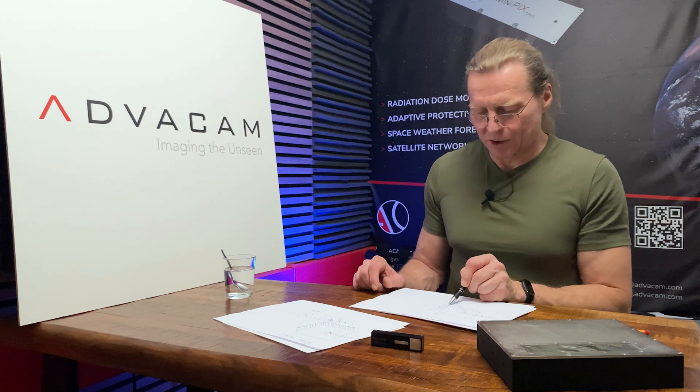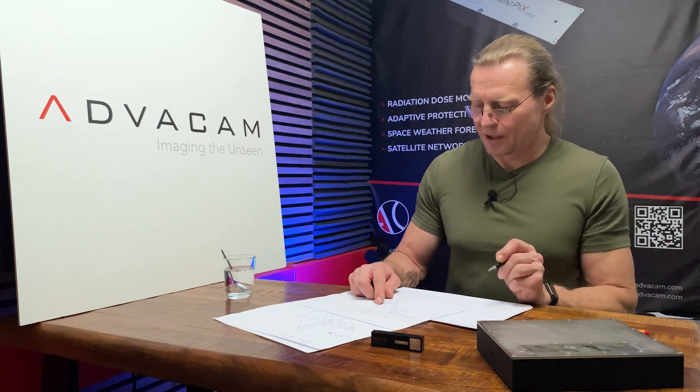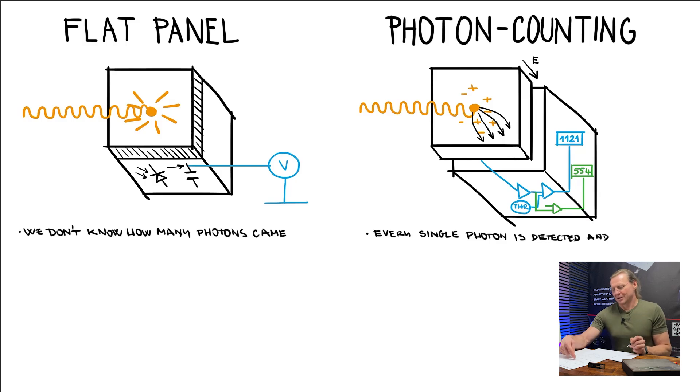The advantage of this technology compared to flat panel, there are a few advantages. The main advantage is that here we really count number of photons. We cannot have better precision than knowing the number of photons. In flat panel, we don't really know how many photons came because each photon generates certain amount of visible light. Then this light has to be converted to electrical signal in photodiode. And then this signal is accumulated in analog memory, which is capacitor. And when measured as a voltage, we don't have a clue how many photons were here. And all those stages are imprecise.